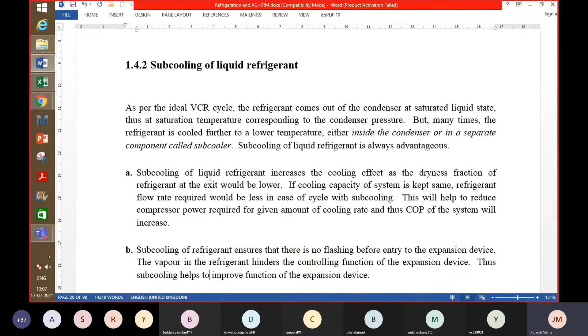After that it enters the throttling device. Now, subcooling is always desirable if it can be achieved, and the higher you can achieve it, the better. But there is a limit to which you can subcool the liquid, because you have to go on increasing the heat exchanger size if you want more and more subcooling. And second, the cooling medium itself has a temperature, and you can never go below that, or even achieve that temperature. There always has to be a temperature difference, and only then will there be heat transfer. But whatever is possible, one should try to achieve.